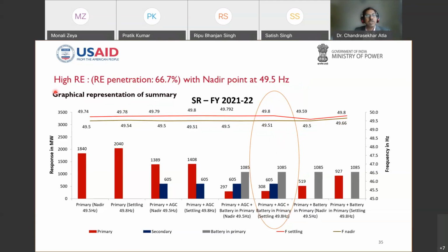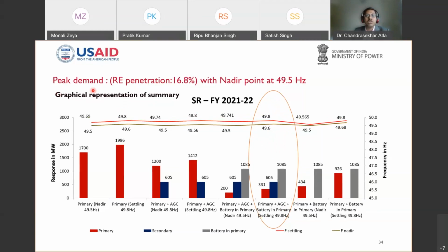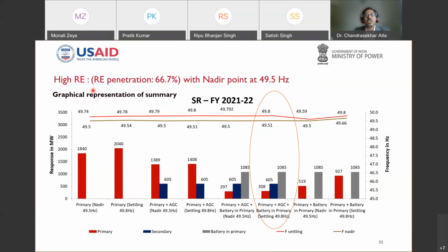Taking it forward, it is the same as the peak load condition which we have seen, but what happens in a high RE scenario? The studies found the high RE condition occurs in different seasons. If solar is more, it will come in January-February, and if wind is more, it will come in July and August, because the southern region wind profile is higher in July and August. Considering those aspects also, the deployment of 1085 battery storage and secondary reserve of 605 will limit the primary participation to 308 instead of 2000 megawatt, and keeps the frequency within the limits. So this was the conclusion we made from the simulation studies.